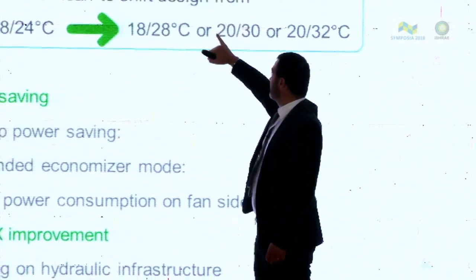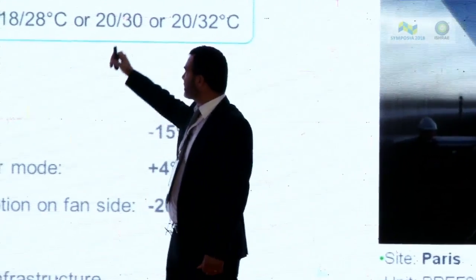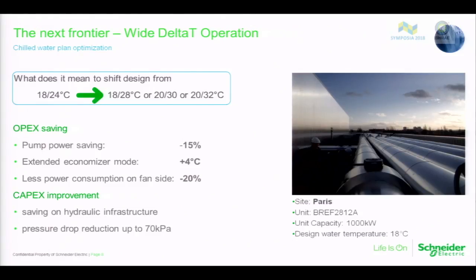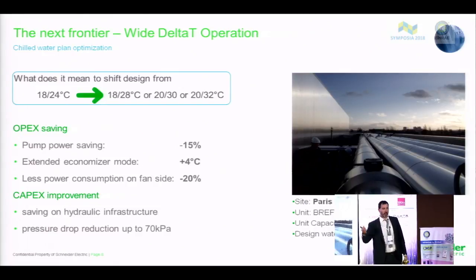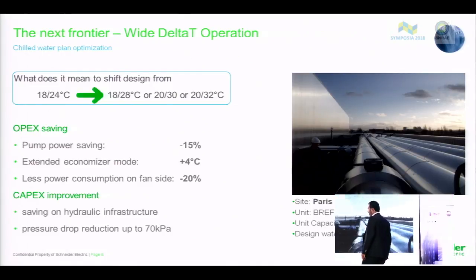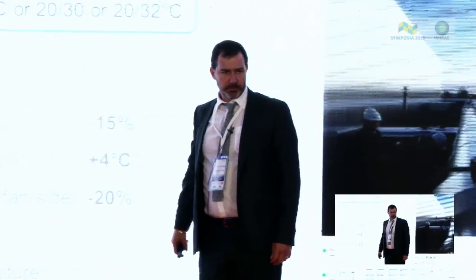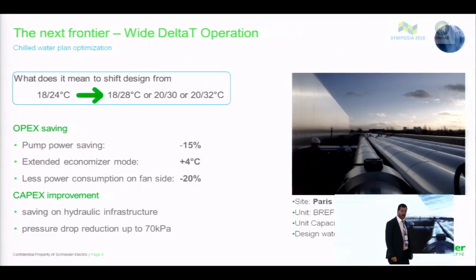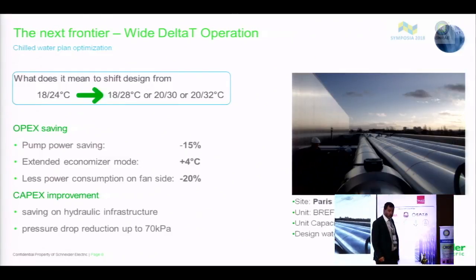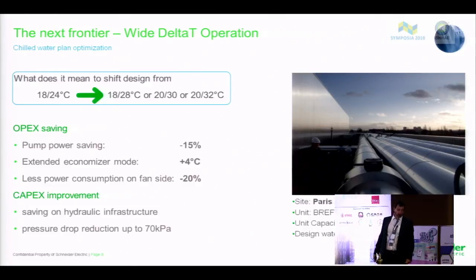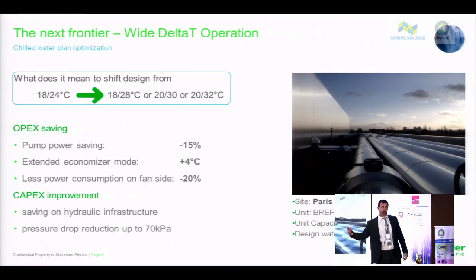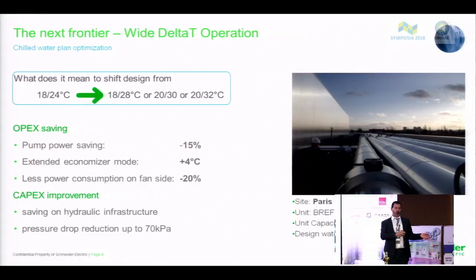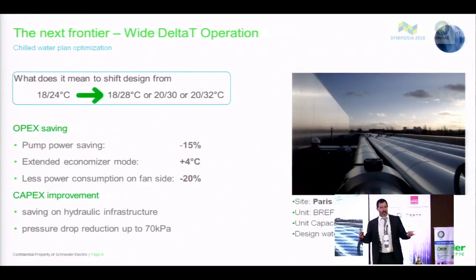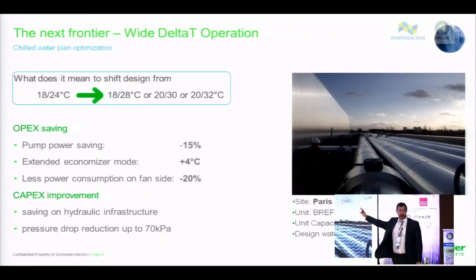And last but not least, if we consider 20/30 or 20/32, since the free cooling on a chiller is based on the return water, and typically in the free cooling units, the free cooling starts when the ambient temperature is colder than the return water. This means that when you design a 20/32 or a 20/30, the free cooling can start at 27. So maybe not Mumbai, but Delhi for sure, Bangalore probably, are good locations for using the free cooling. So even if 10 years ago, 5 years ago, free cooling on a chiller in India was used seldom or not extremely efficient, with those conditions, it changed completely the scenario.